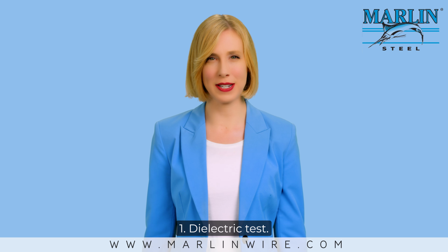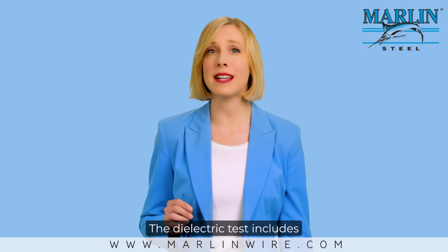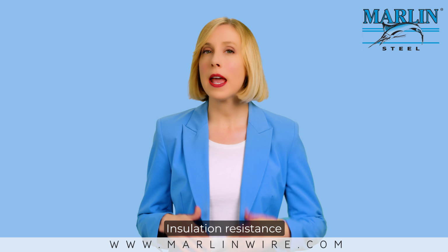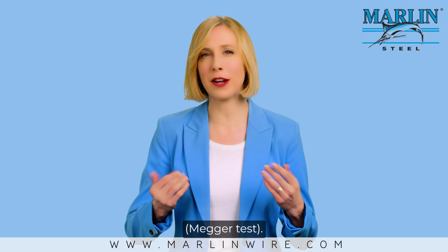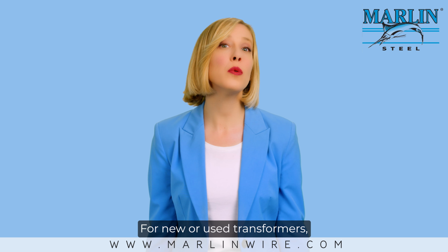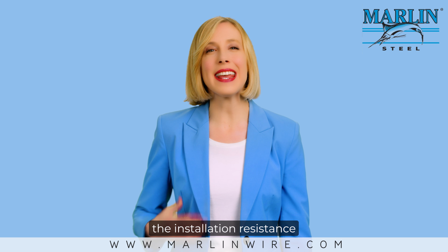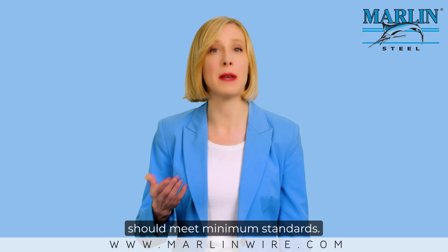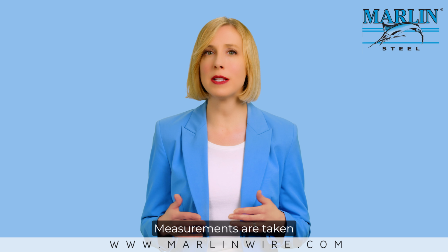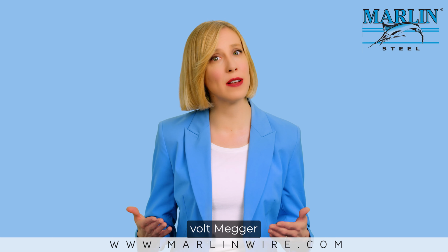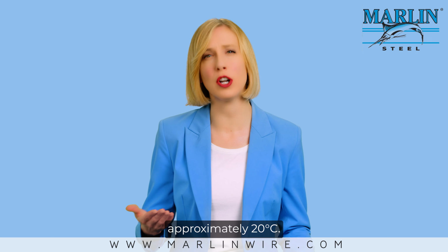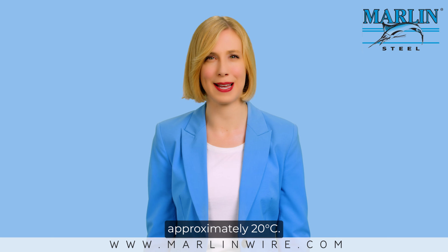1. Dielectric test. The dielectric test includes two parts: insulation resistance, Megger test. For new or used transformers, the insulation resistance should meet minimum standards. Measurements are taken with a 500 or 1000 volt Megger at room temperature, approximately 20 degrees Celsius.